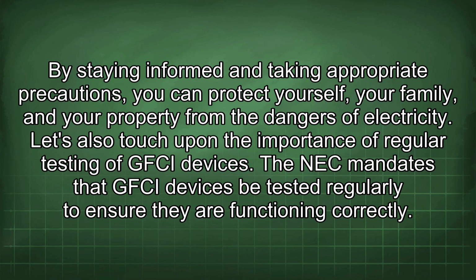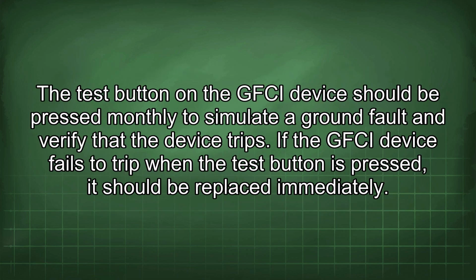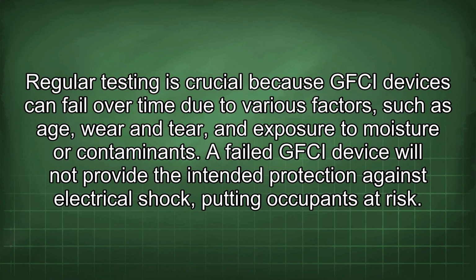Let's also touch upon the importance of regular testing of GFCI devices. The NEC mandates that GFCI devices be tested regularly to ensure they are functioning correctly. The test button on the GFCI device should be pressed monthly to simulate a ground fault and verify that the device trips. If the GFCI device fails to trip when the test button is pressed, it should be replaced immediately. Regular testing is crucial because GFCI devices can fail over time due to various factors such as age, wear and tear, and exposure to moisture or contaminants. A failed GFCI device will not provide the intended protection against electrical shock, putting occupants at risk.